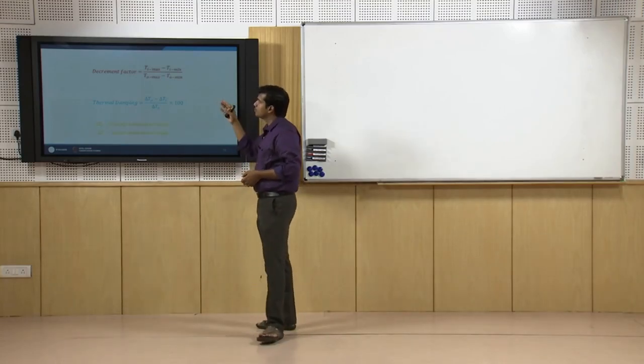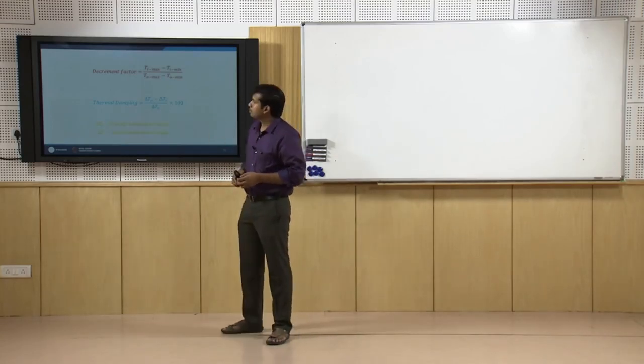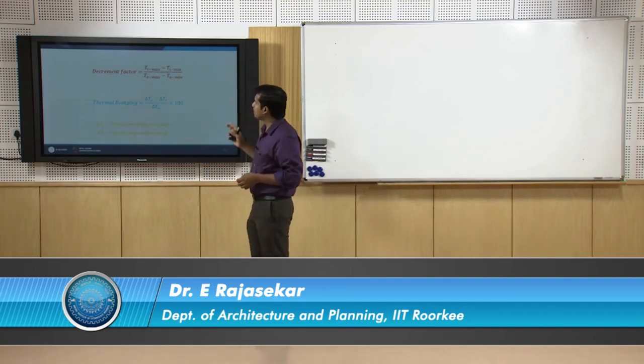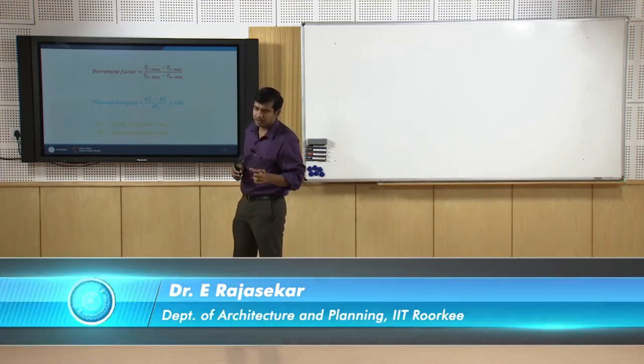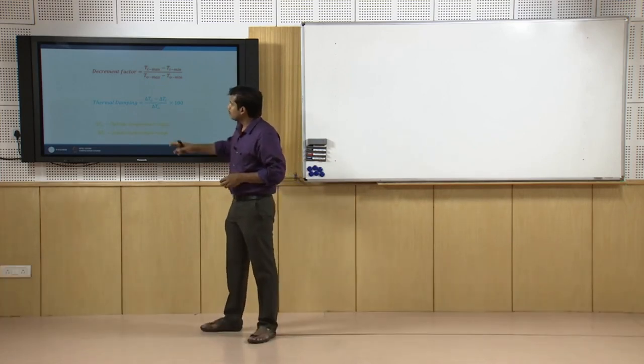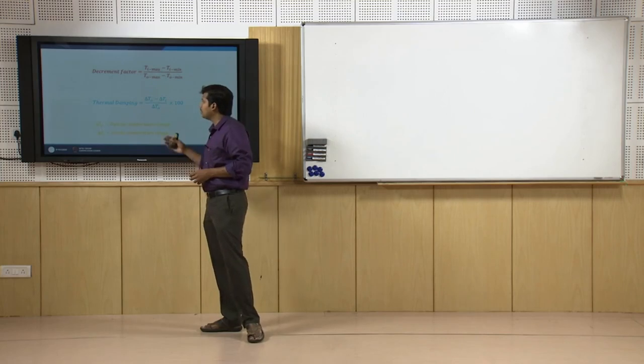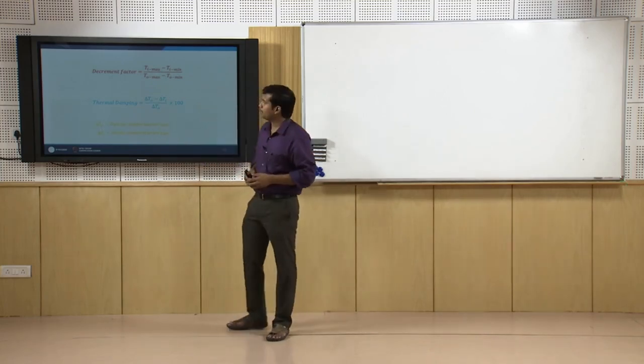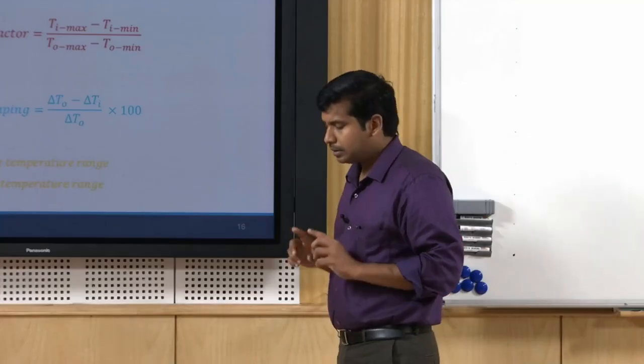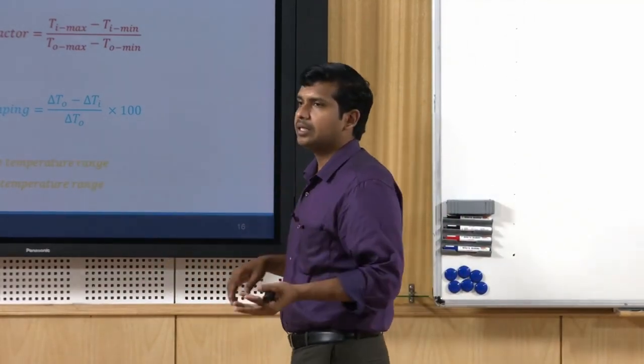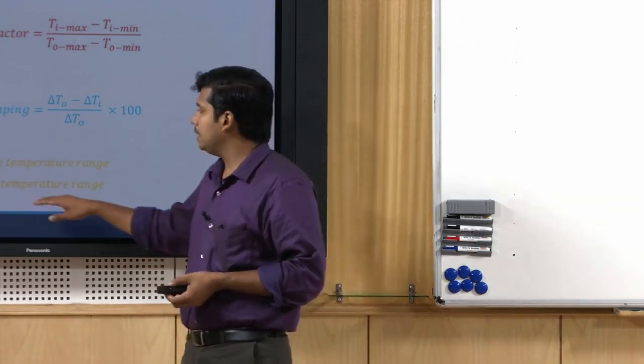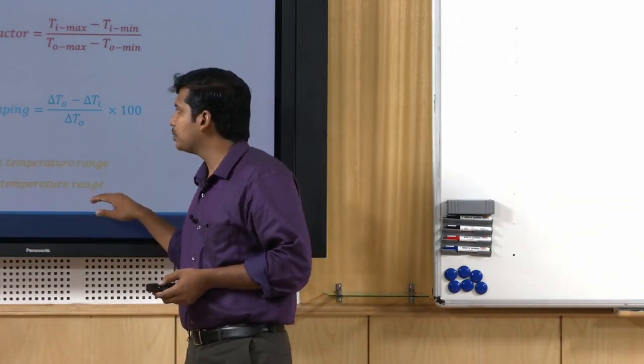In the previous session we stopped looking at decrement factor, which is the outside surface inside surface delta T — T_i_max minus T_i_min divided by outside surface delta T — T_o_max minus T_o_min — which is a number between 0 and 1. The Indian national building code talks about thermal damping: it uses delta T_o, which is outside air temperature range, not surface temperature — the outside temperature amplitude versus the inside air temperature diurnal temperature amplitude.